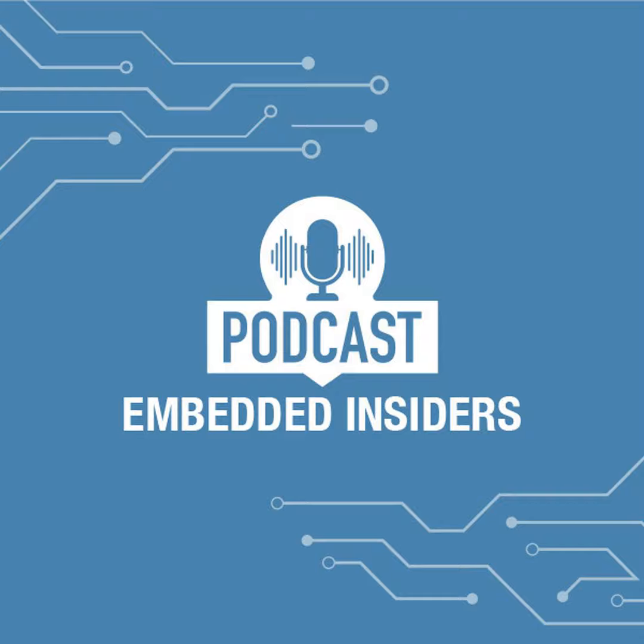And for our listeners not in the U.S., which we do have some, do you guys work in the regulatory structures that are different for the EU or in China and parts of Asia? Do you also work in that regulatory space? Definitely, yes. We've got different folks at Microchip throughout the globe that are also medical subject matter experts, like we call ourselves for the company. I've got somebody who handles Europe for the EU MDR. And then we've got different locations throughout other parts of the world that have their own regulatory approval process for medical devices. They all started out similar to the FDA, so there's still a lot of things in common, but there's been variations over the years. The EU in particular is going their own way in some respects, but the basic premise is the same, and just how you go about it might be a little different. Of course, I know the EU focuses very heavily on the privacy side, so that becomes a challenge. But let's stick to the U.S.